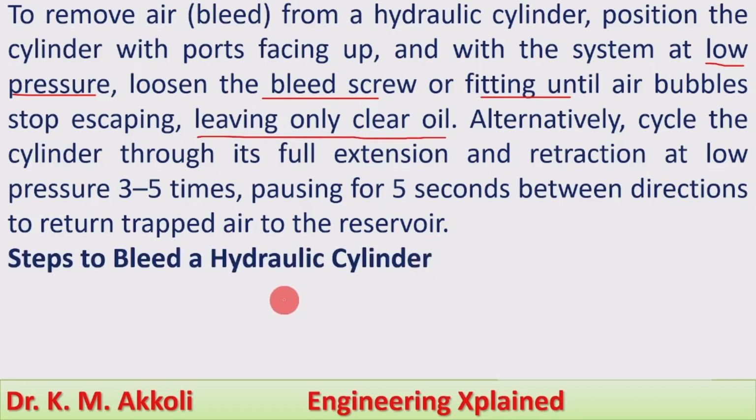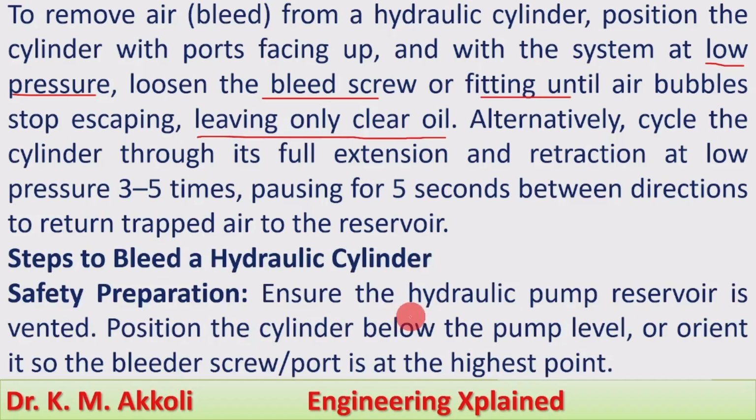Here are the steps to bleed the hydraulic cylinder. First one, safety preparation. What safety preparation is required? Ensure the hydraulic pump reservoir is vented. Usually the reservoir is vented in order to maintain atmospheric pressure, so the vent should be checked for this pump reservoir.